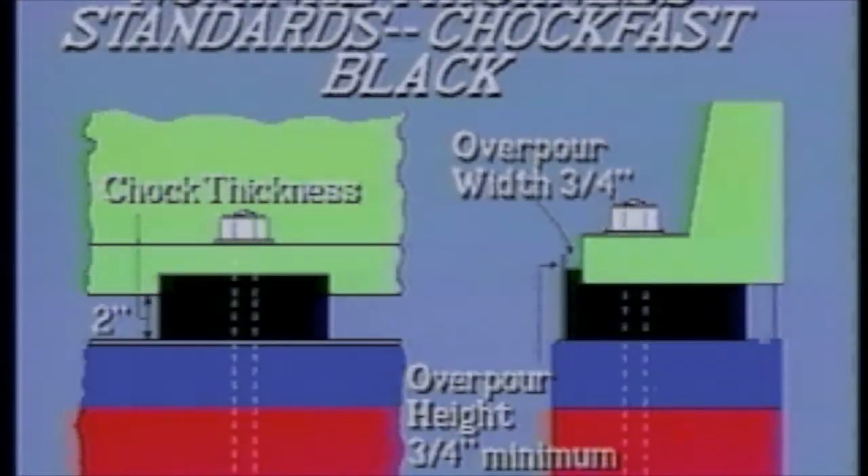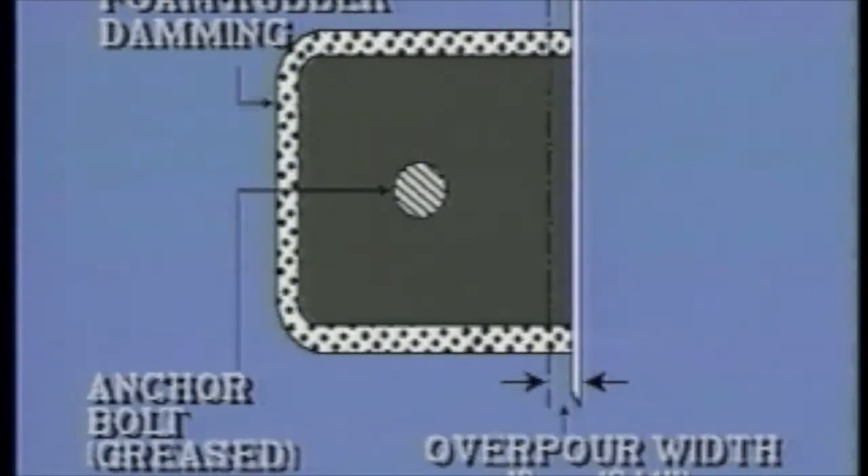Since Chockfast Black is poured in place, it offers maximum surface contact — virtually 100% — with the underside of equipment bed plates, far superior to steel chocks. Chockfast Black is poured to a minimum thickness of 2 inches with an overpour width of 3/4 of an inch and overpour height of 3/4 of an inch. This overpour is critical in assuring that maximum surface contact with the bed plate is achieved.